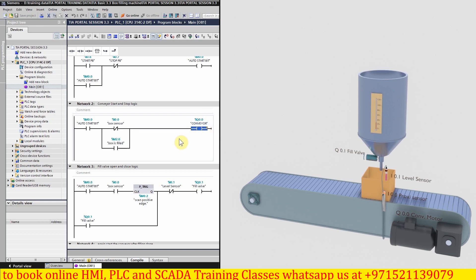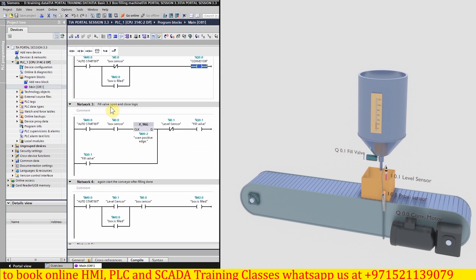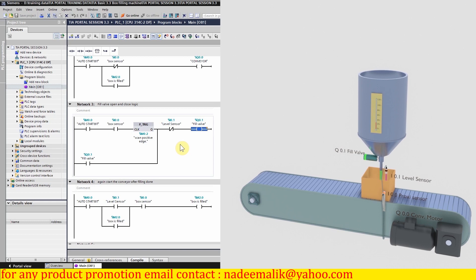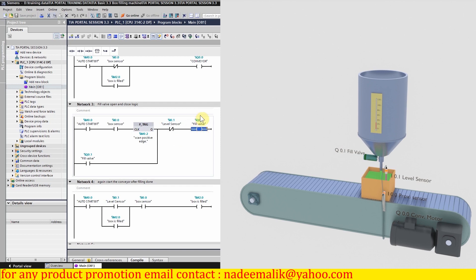In network number three we have the logic to open and close the fill valve. We insert the auto start bit M 0.0, and when the box is present in front of sensor I 0.0, on the rising edge of I 0.0 it latches on the fill valve Q 0.1 and starts pouring liquid into the box. Once the fill level is achieved, confirmed by level sensor I 0.1, we use a normally closed contact — once the fill level is achieved, this normally closed contact opens, turns off output Q 0.1, and the fill valve closes.